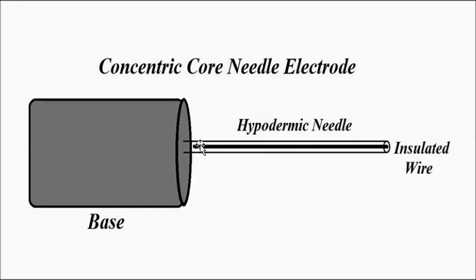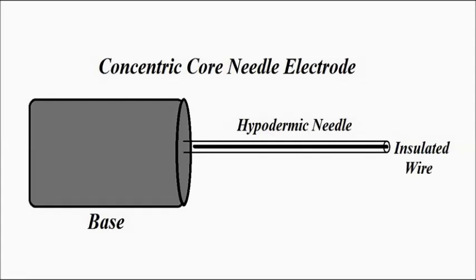Here you can see the concentric core needle electrode: this is the hypodermic needle, and inside it we have the insulated platinum wire which is exposed at the tip. This also has a lead wire for signal conduction and feeding to the signal conditioning and processing circuitry — I have just forgotten to draw it here, but it is present. The hypodermic needle in the form of a cylinder containing the insulated wire exposed at the tip is what distinguishes it from the other electrode types.